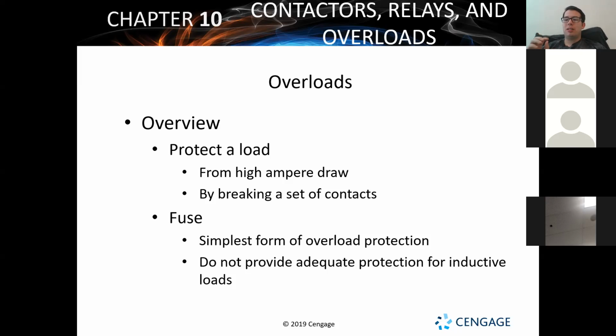The easiest thing instead of getting a bunch of 3 amp or 5 amp fuses, they've got a resettable fuse you can buy called a pop-up, and that's the easiest thing in the world for diagnosing low voltage electrical problems. You hook the pop-up fuse in the same spot as a regular fuse, and if the amperage gets too high, it'll pop up a button. But if the amperage is low enough, it'll let power continue to pass through until you find your issue. That helps a lot because replacing fuse after fuse is just a waste of time, money, and supplies you don't need to use.